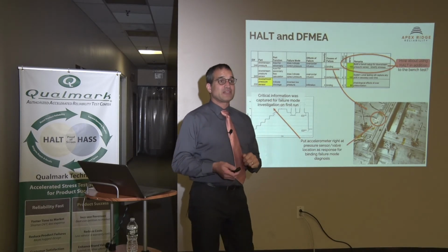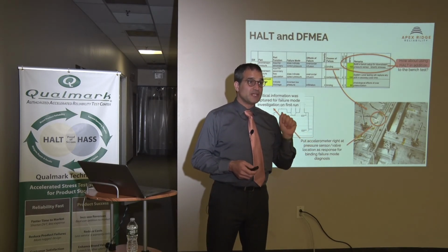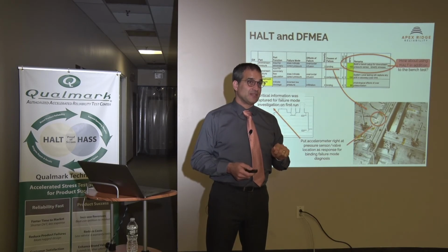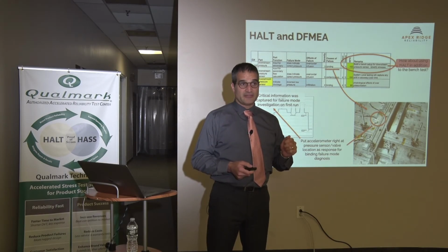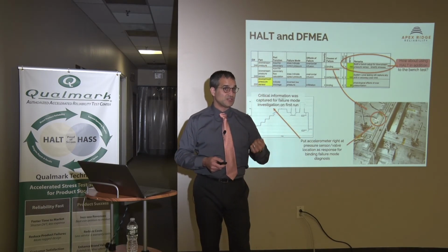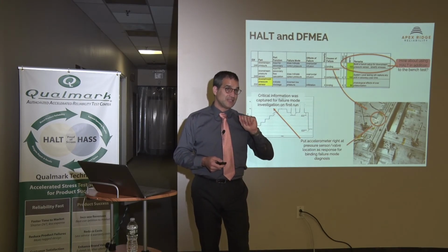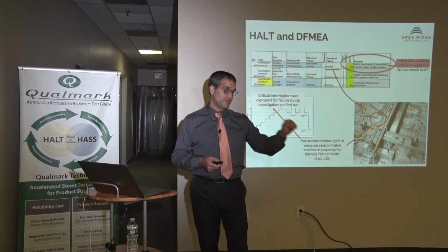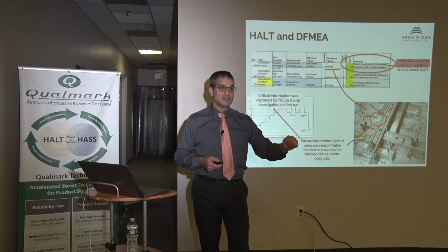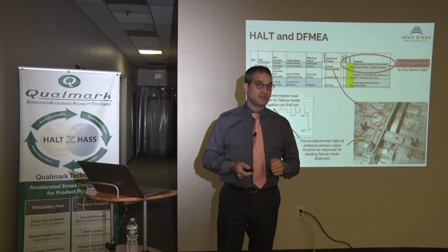And let's say this is a medical device. Incorrect pressure can give a doctor information where they killed a patient because they are not understanding what's happening. So it's not just an inconvenience, it can be life or death. And I've actually experienced this type of thing regularly with medical devices and simple sensors. These are sensors that are disposable, by the way, right? A lot of medical products have components that are disposable, especially if they interface with the patient, right? Because that's one of the easiest ways to deal with being sanitary. So here you have disposable sensors that if they give the wrong signal, you can kill somebody.